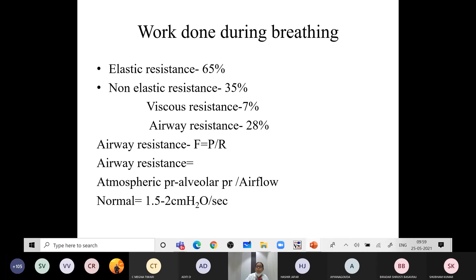Now coming on to the factors affecting the airflow resistance. Airflow resistance is inversely proportional to the total cross-sectional area. That means airflow resistance increases when the total cross-sectional area decreases, and resistance decreases if the cross-sectional area is increased.